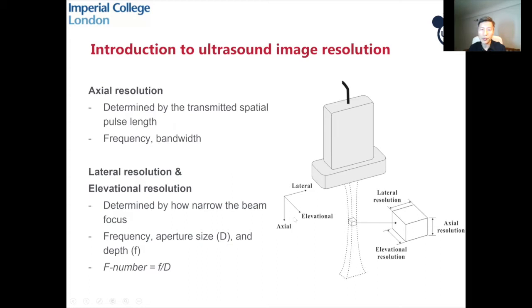The aperture size in the elevational and lateral directions, and also the depth — the depth of your point of interest. In ultrasound imaging, we quite often use a number called F-number, which is the depth of interest divided by the aperture size. This is important in determining the lateral and the elevational resolution.